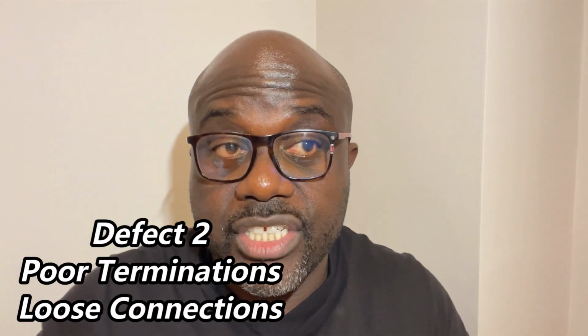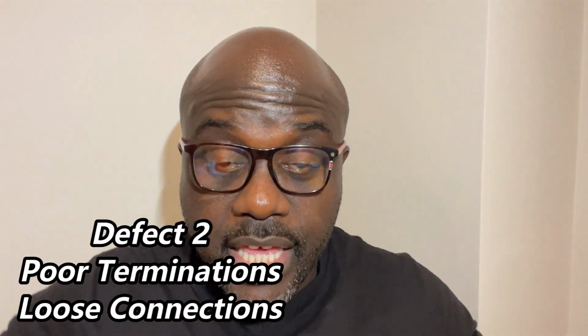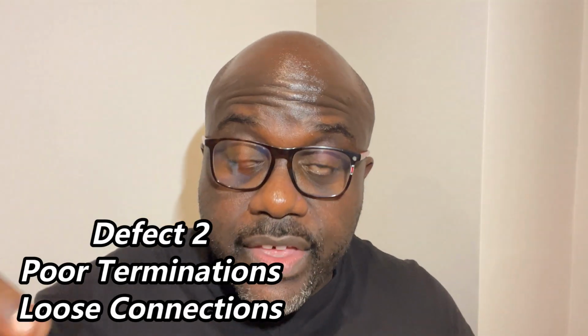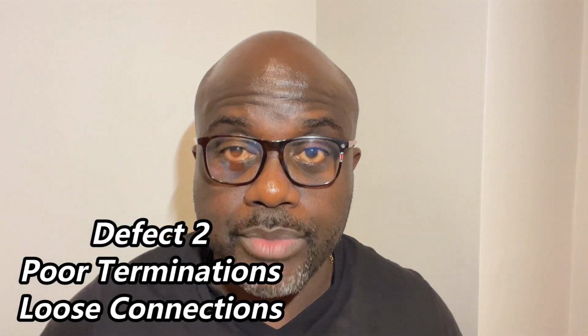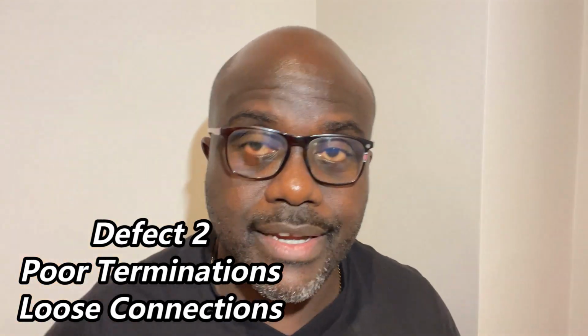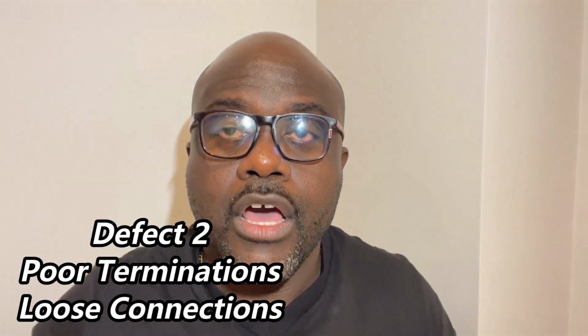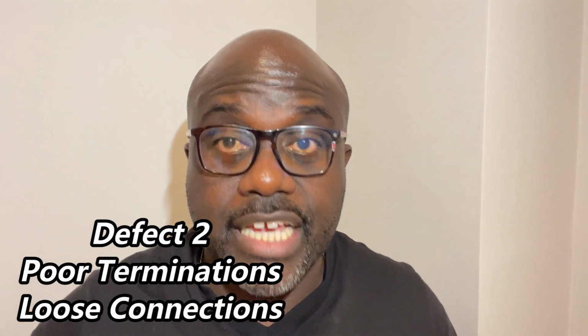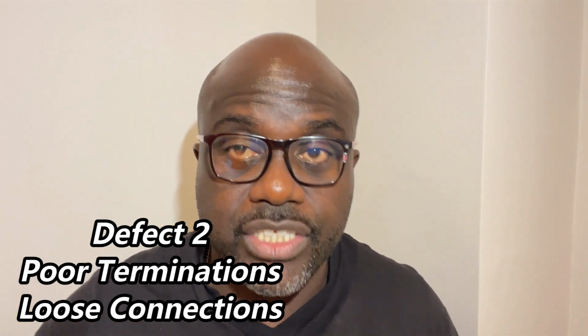Defect number two, guys: poor terminations and loose connections. Loose terminations are fire starters. So even at the distribution board, when the electrician has put the cables into the breakers, before the power comes on, you can do a little tug on the cables to check the firmness of the cables, or get the electrician to check it to make sure everything is firm and there's no loose connections, no loose terminals in junction boxes, no loose connections in sockets, no screws left in live distribution boards, for example. These are all fire starters.